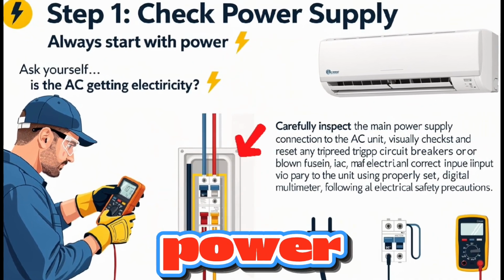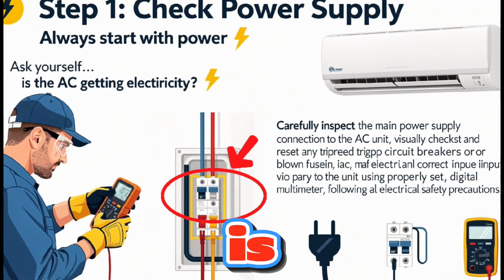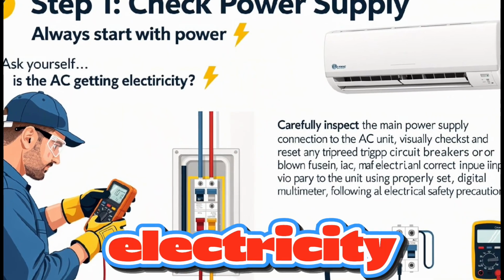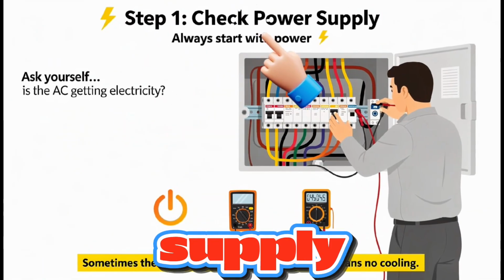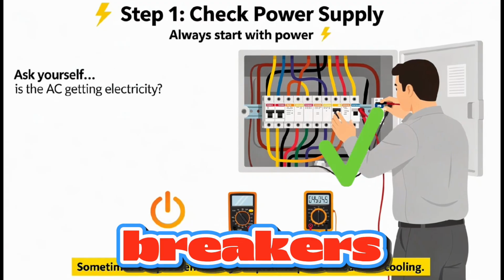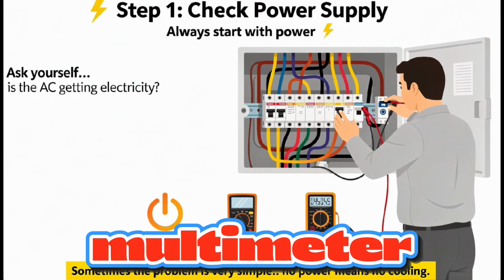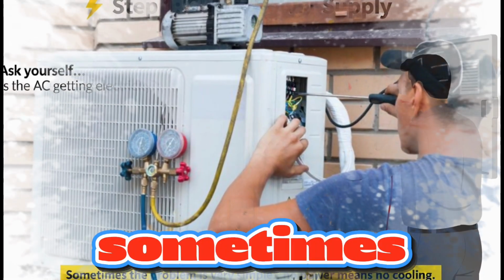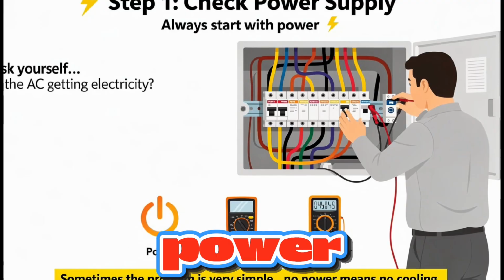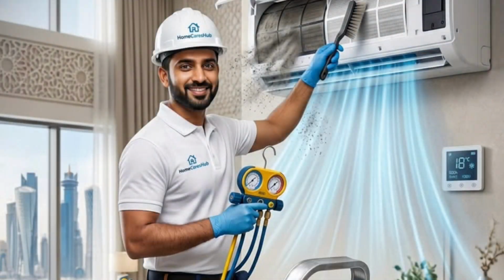Always start with power. Ask yourself, is the AC getting electricity? Check the main supply, inspect circuit breakers, and confirm voltage using a multimeter. Sometimes the problem is very simple. No power means no cooling.